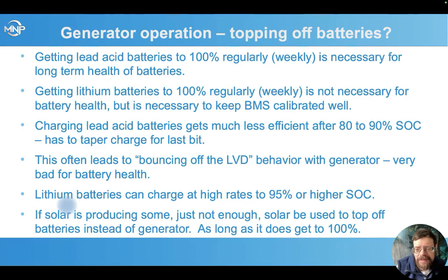So it's a lot easier to get them very close to full and then just let the solar top them off. If you really don't have any solar input, then you may need to really get them to 100%, say once a week with the generator. But if you've got some solar input, it's a lot more amenable with lithium batteries to get them pretty close and let solar finish it up, and not really be worried about damaging your batteries like we had the issues with lead acid batteries, where not getting them full really led to sulfation and poor lifespan.